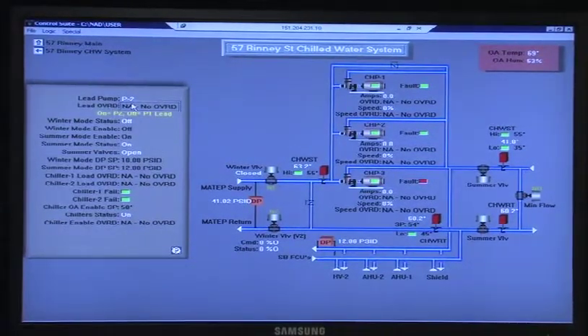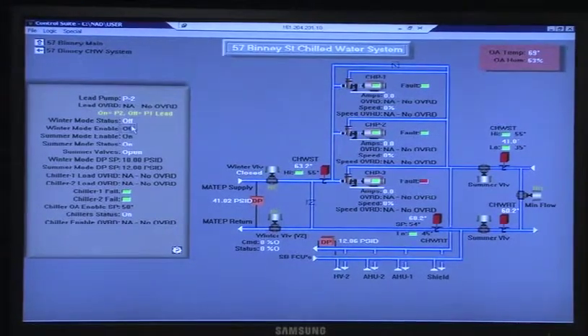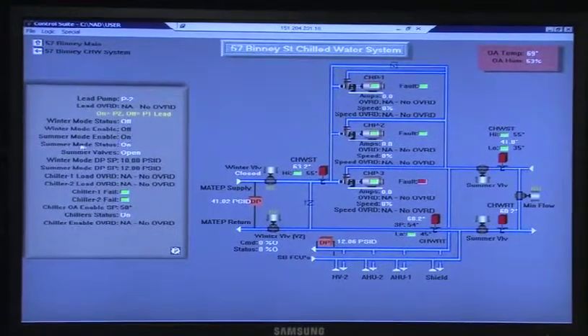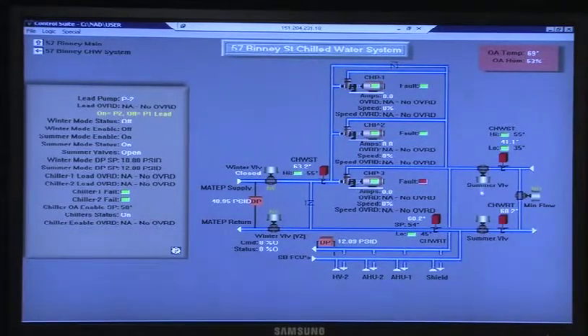If we look up here, we have P1, the winter mode is off. Winter mode enables off. Summer mode is on. So I just want to step through this for a minute. The valves are open. If you look here, these valves here, summer valve, these are actually open.